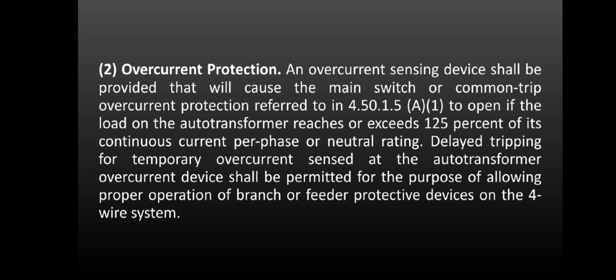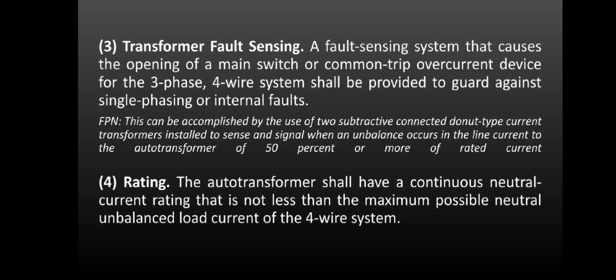2. Overcurrent protection. An overcurrent sensing device shall be provided that will cause the main switch or common trip overcurrent protection referred to in 4.50.1.5 to open if the load of the autotransformer reaches or exceeds 125% of its continuous current per-phase or neutral rating. Delayed tripping for temporary overcurrents sensed at the transformer overcurrent device shall be permitted for the purpose of allowing proper operation of branch or feeder protective devices on the four-wire system. 3. Transformer fault sensing. A fault sensing system that causes the opening of the main switch or common trip overcurrent device for the three-phase, four-wire system shall be provided to guard against single-phasing or internal faults. 4. Rating. The autotransformer shall have a continuous neutral current rating that is not less than the maximum possible neutral unbalanced load current of the four-wire system.